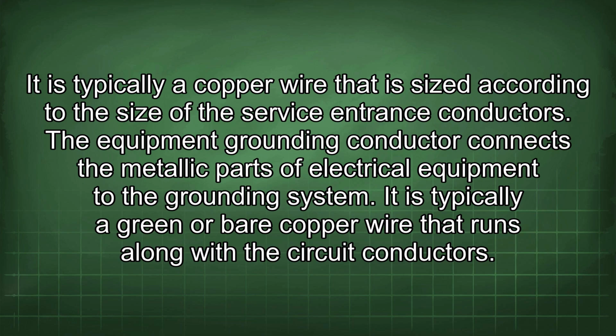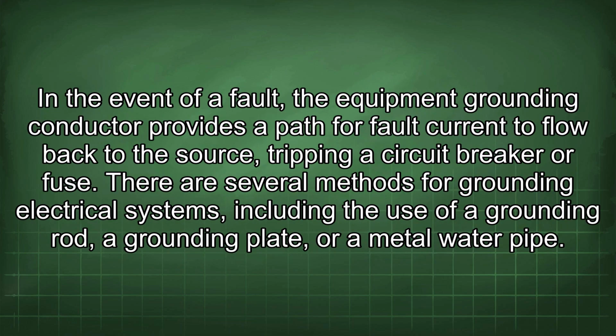The equipment grounding conductor connects the metallic parts of electrical equipment to the grounding system. It is typically a green or bare copper wire that runs along with the circuit conductors. In the event of a fault, the equipment grounding conductor provides a path for fault current to flow back to the source, tripping a circuit breaker or fuse.